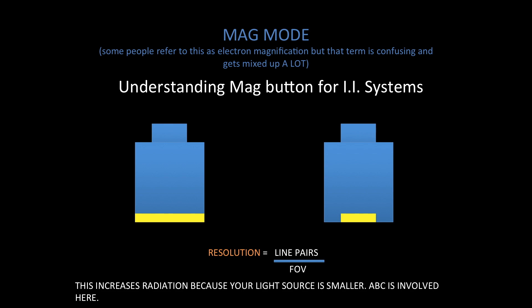The other important aspect of magnification mode is that because you have a smaller light source you will need to increase the radiation dose to the patient. This is usually done automatically nowadays by the ABC system. ABC stands for automatic brightness control, and that brightness control is a light sensor that will detect the need for increased radiation — an increased number of photons — usually achieved by increasing your mA, but it can also increase kVp. Be aware that there is an increase in radiation anytime you're doing magnification.